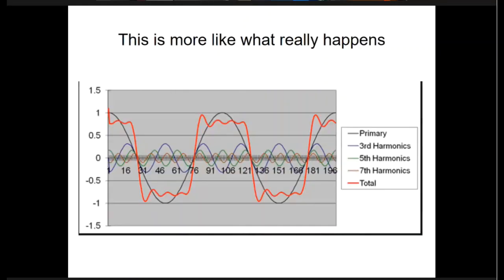Okay, so here's what is more likely. You have not just second harmonic, but third, fifth, seventh, all can be distorted depending on if you have certain kinds of motors, compressors, especially air conditioning, or refrigerators, or electronic motors of some sort—they can generate harmonics. A lot of them have filters to suppress the harmonic going back into the power line, but not everyone does. That's more likely the kind of waveform you start to see when you have a lot of noise. I've looked at one and it doesn't even look as regular as this.